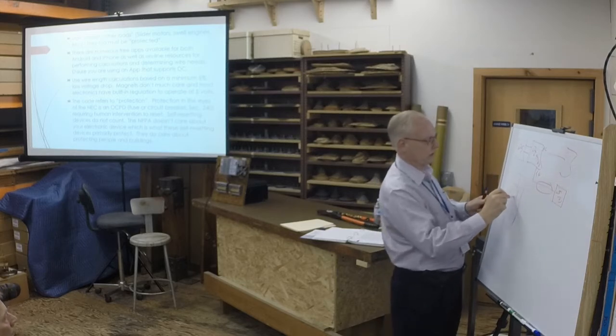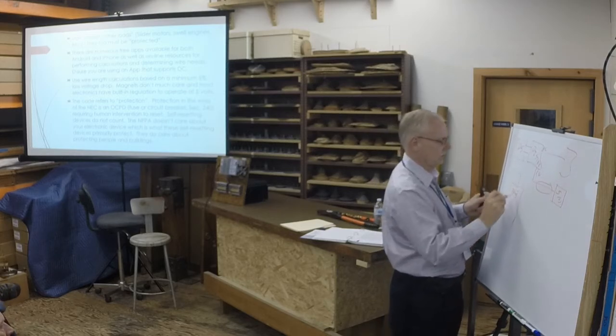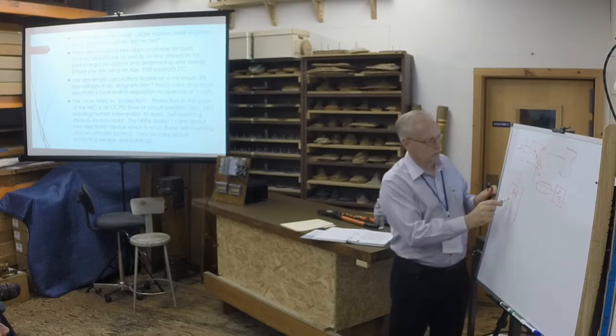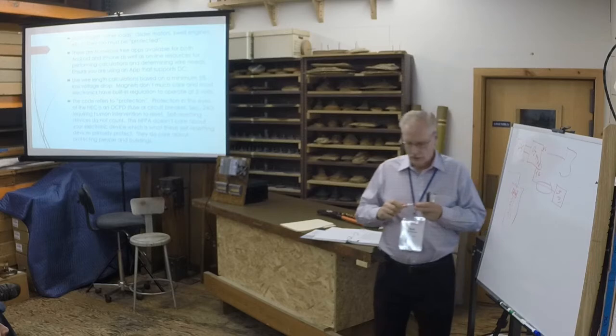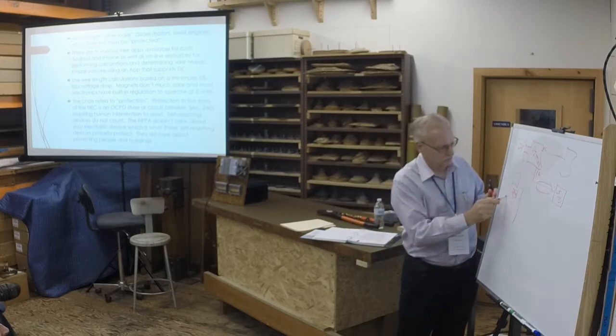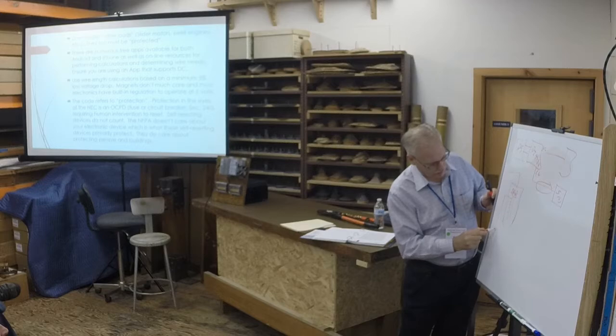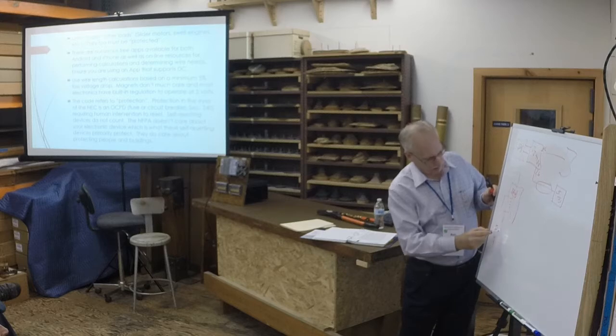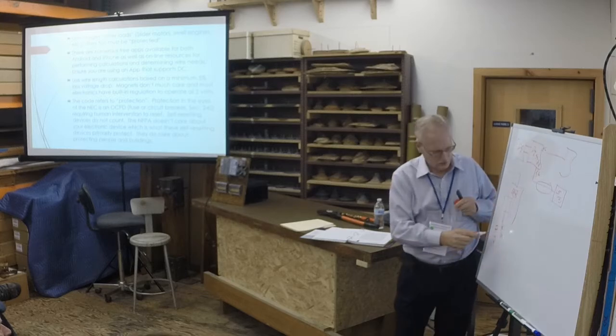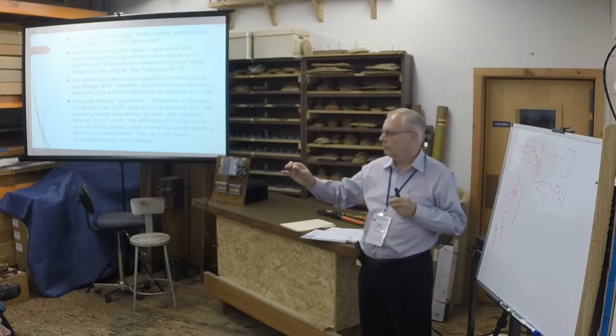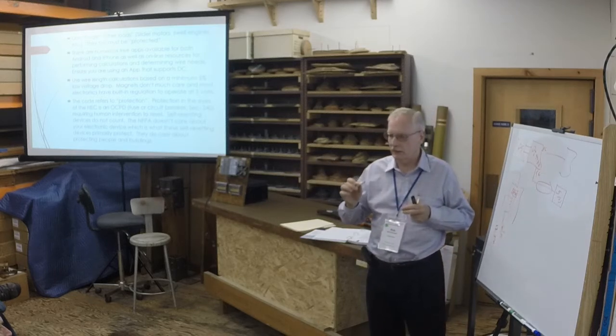Power comes in from the street, you've got a main. You've got 2 buses, each one has a circuit breaker, each step of protection. Let's say that's a 20 gauge or 12 gauge wire, so under the code that's a 20 amp circuit. But that's a 15 amp breaker there, so that's a 14 gauge wire, that's a 15 amp circuit. Every step of the way, you're fusing to the current carrying capacity of the wire.